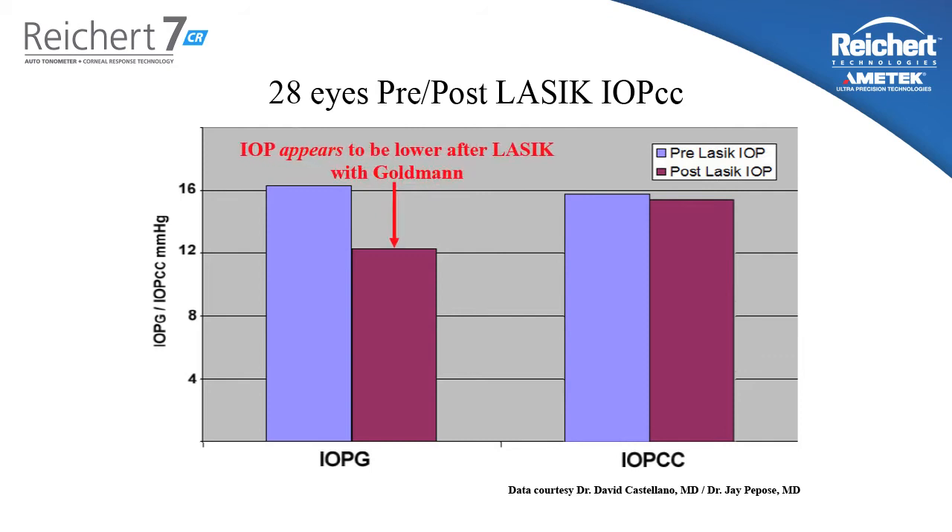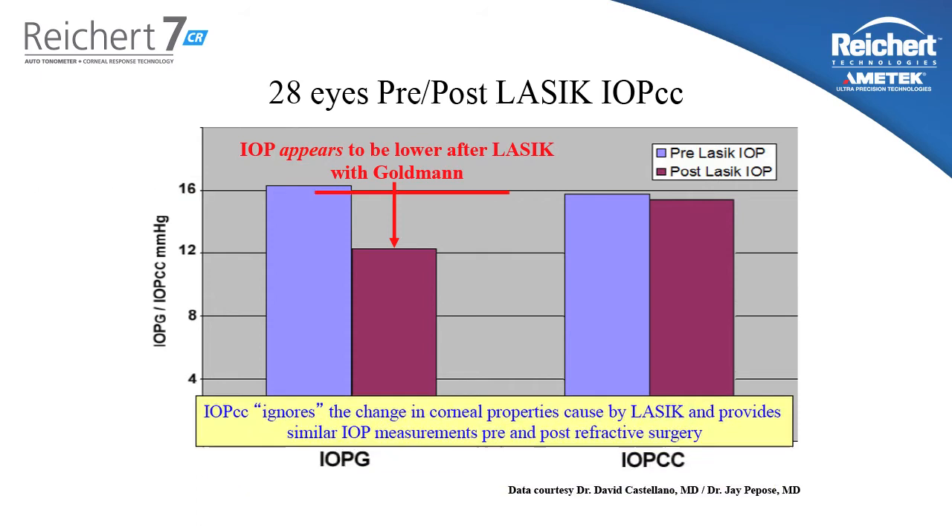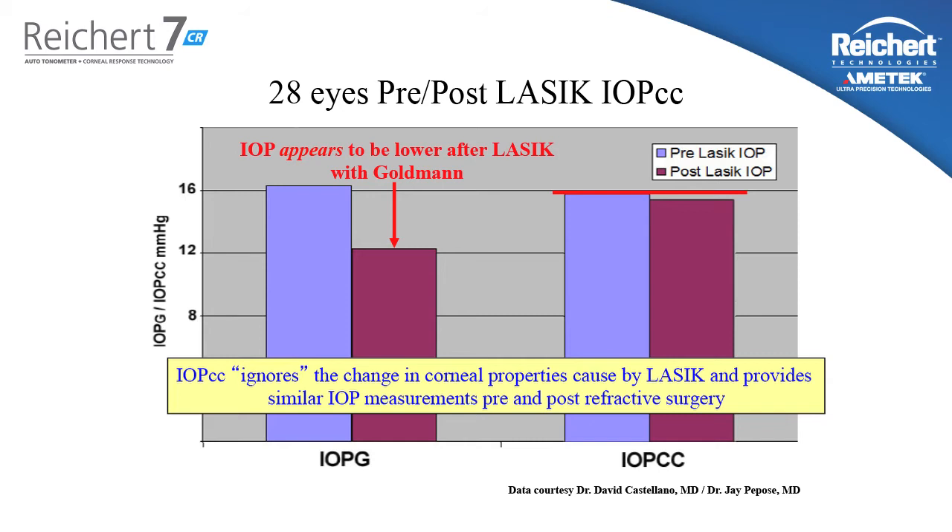Here we see data from 28 eyes pre and post LASIK. Looking at the Goldmann measured IOP, it appears that after LASIK surgery the measured pressure is approximately 4 millimeters lower than prior. However, the IOPCC measurement does not change after refractive surgery. While the IOPCC measurement agrees with Goldmann on average, it has very little correlation with corneal thickness, stays fairly constant after refractive surgery, and most importantly, it is better correlated with the status of glaucoma than Goldmann tonometry itself.